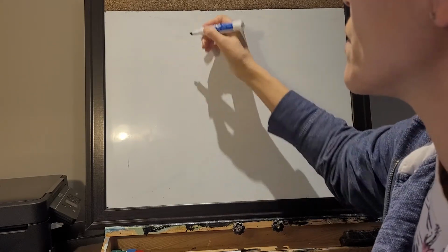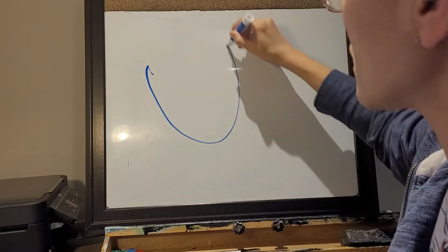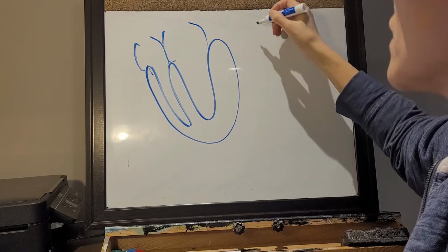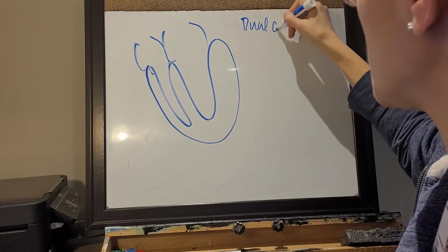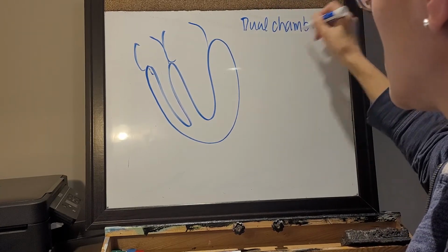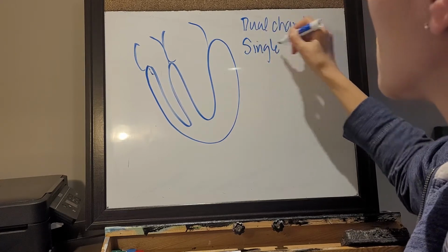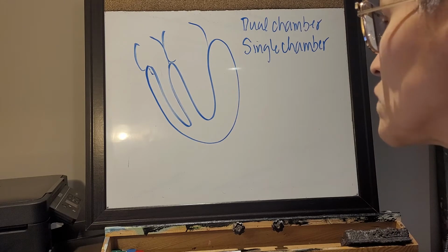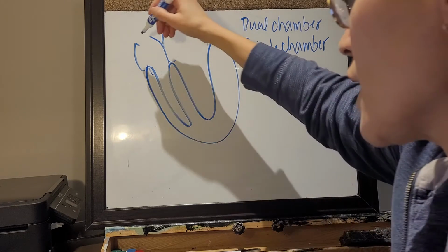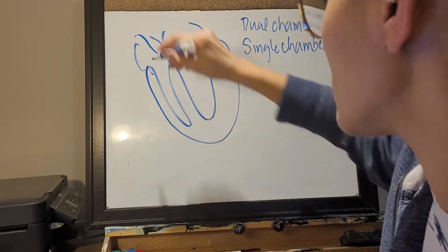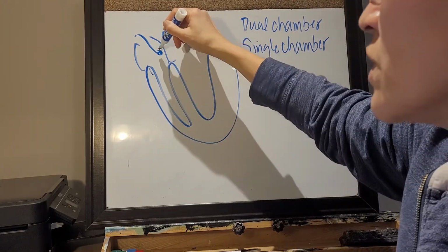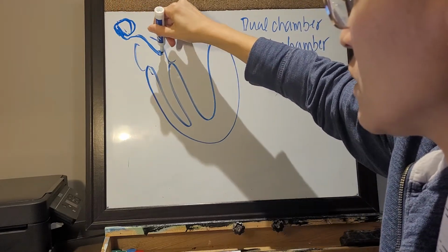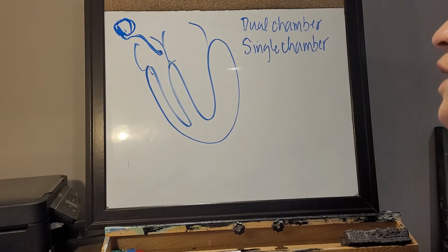So if you have a pacemaker, and we talk about having dual chamber, single chamber. Chamber just refers to the chamber of the heart where the pacemaker lead might be lying. And we might have just an atrial lead. So we'll have a single chamber pacemaker with an atrial lead. I'll put the pulse generator up here. And you have the lead into the heart here.